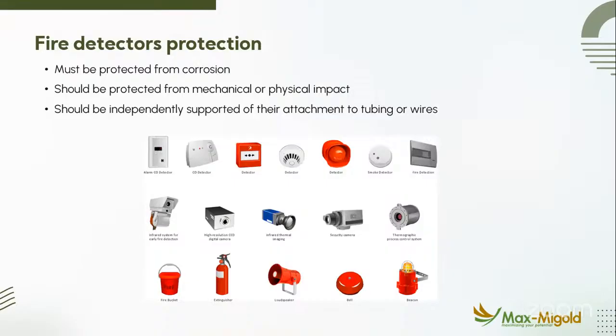You can see examples of components of fire detectors. We're saying that you should protect the detectors from corrosion, from physical impact or mechanical impact, and that you should ensure that there is continuity in the wiring, which you can confirm by testing. So basically, don't put the smoke detectors where a vehicle, maybe a manual handling equipment, like a pallet stacker, a hand jack or what have you, or even a forklift, genie boom, skyjack can actually collide with it. You must ensure that there's no collision, physical impact that can result in physical damage. And also, don't put smoke detectors under the rain. It will damage them, or even your panel. You get them damaged so quickly. Next slide.